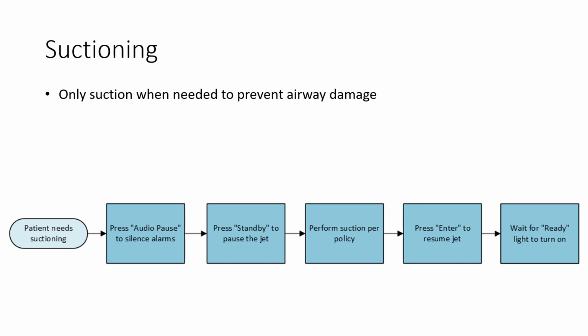To suction, first press the audio paused button to silence alarms. Next, press standby to pause the jet ventilator. This prevents any alarms and errors associated with pressure fluctuations. Now suction according to hospital policy. Next, press Enter to resume the previous jet settings. When the ready light turns on, ensure that the settings are appropriate and the procedure is complete.